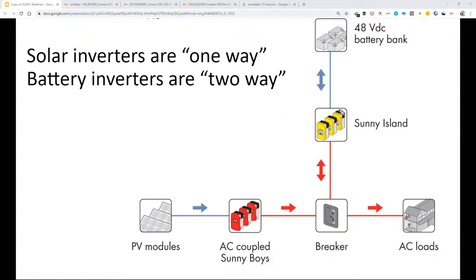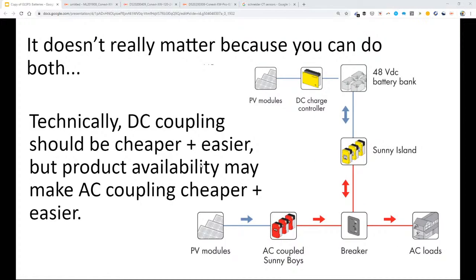Fundamentally, on most battery inverters there are batteries and load panels that have tremendous one-way battery management function from the battery system's viewpoint. But on the grid side—where the battery inverter gets its charge and sometimes outflows to—that can be really dumb, poor, not very smart. Most solar inverters, to begin with, are dumb and don't have much intelligence for backfeeding the grid. To do advanced smart features with your battery system's output, you need not just a battery inverter, but one smarter than average. That can surprise some people, and we'll give you some examples.